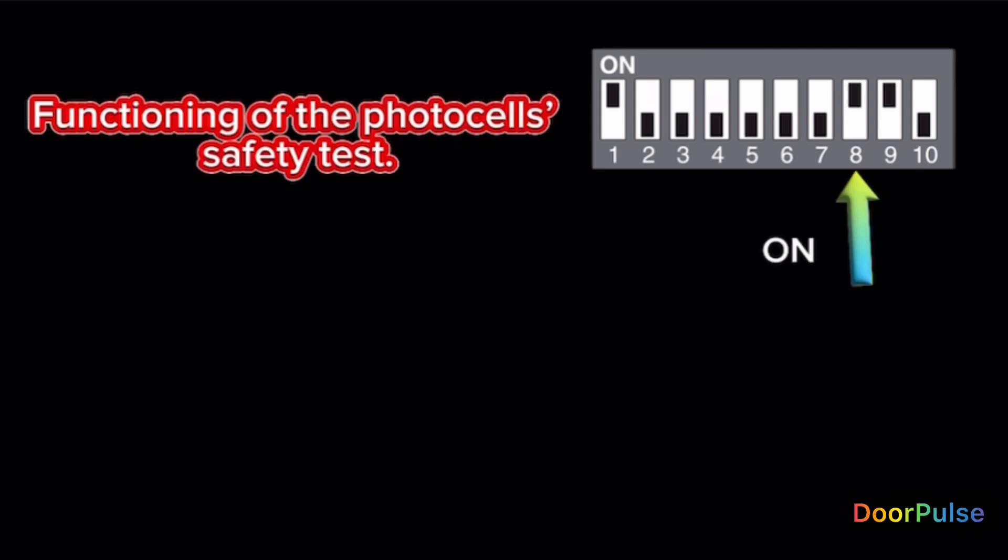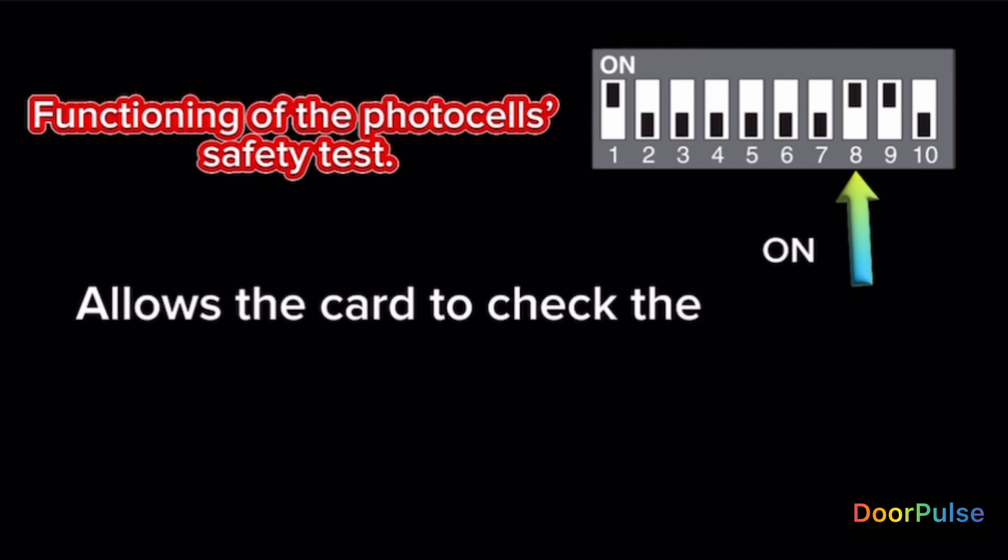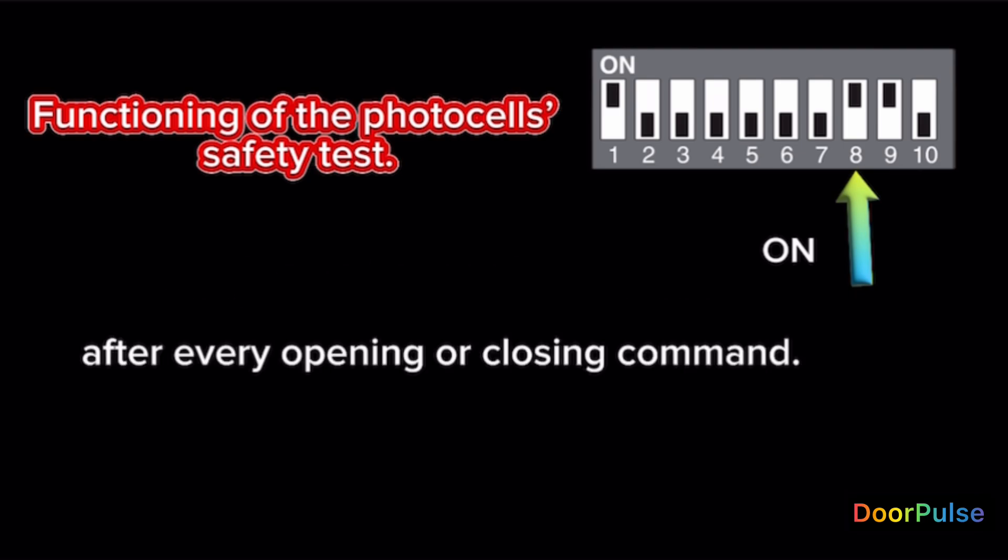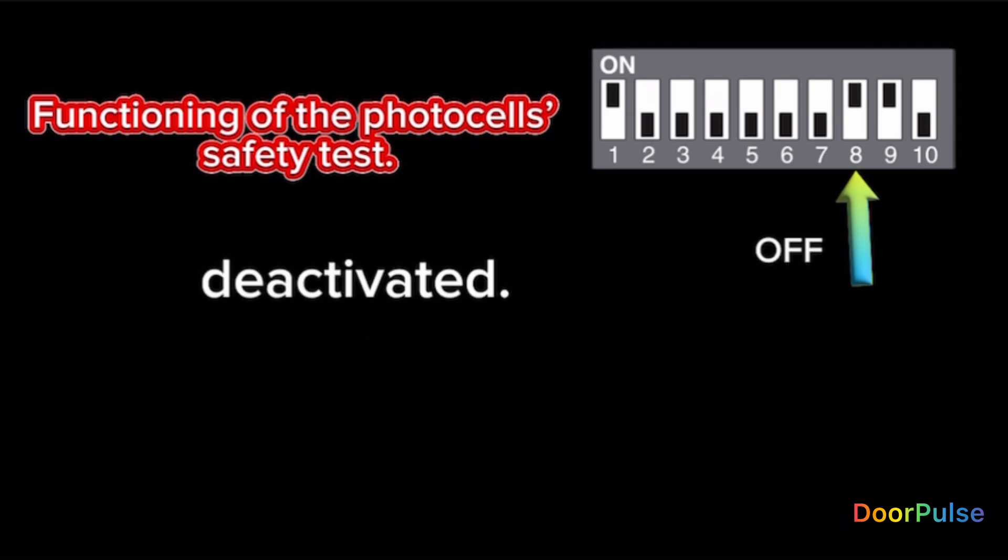Switch 8 ON. Functioning of the photocells safety test. Allows the card to check the efficiency of any safety devices, i.e. photocells, after every opening or closing command. Switch 8 OFF. Deactivated.